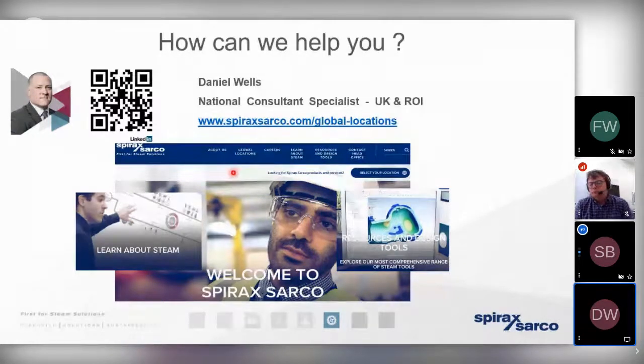Lovely. Thank you. And there's another question here from Alan with regard to pressure control, pressure reduction, I guess really, is what we're talking about. And it says, Dan, with using pressure to control the steam temperature, what happens when the steam goes through a pressure reducing valve? If the temperature is reduced, where does the excess heat energy go? Yep, that's a very good question.